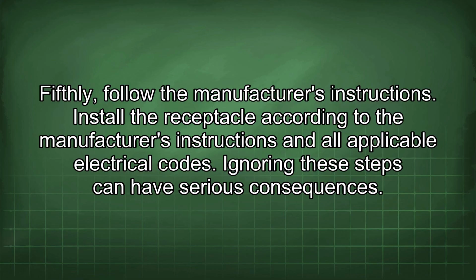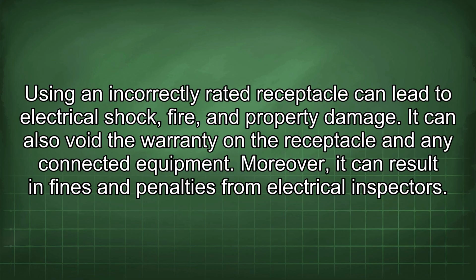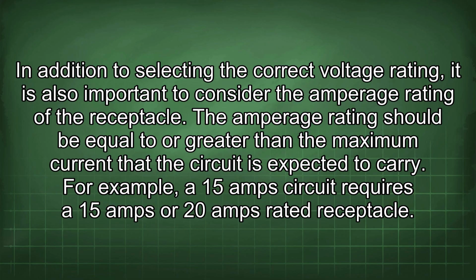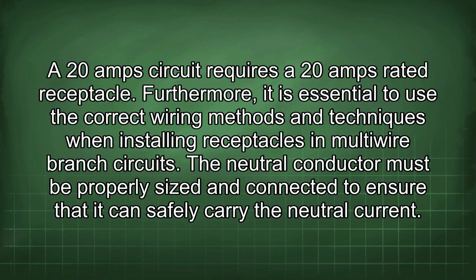Ignoring these steps can have serious consequences. Using an incorrectly rated receptacle can lead to electrical shock, fire, and property damage. It can also void the warranty on the receptacle and any connected equipment. Moreover, it can result in fines and penalties from electrical inspectors. In addition to selecting the correct voltage rating, it is also important to consider the amperage rating of the receptacle. The amperage rating should be equal to or greater than the maximum current that the circuit is expected to carry. For example, a 15 amp circuit requires a 15 amps or 20 amps rated receptacle. A 20 amp circuit requires a 20 amps rated receptacle.